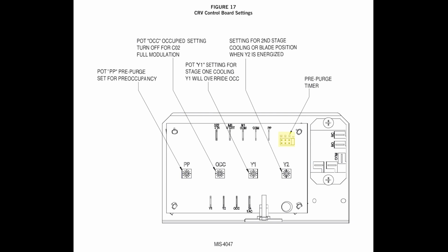The pre-purge timer factory default is shipped on 0, and the small jumper must be placed on the correct pins to set the pre-purge pot switch. California Title 24 requires 3 complete air changes within 60 minutes. The pre-purge timer jumper would be set and left on 60 when setting the pre-purge pot switch.